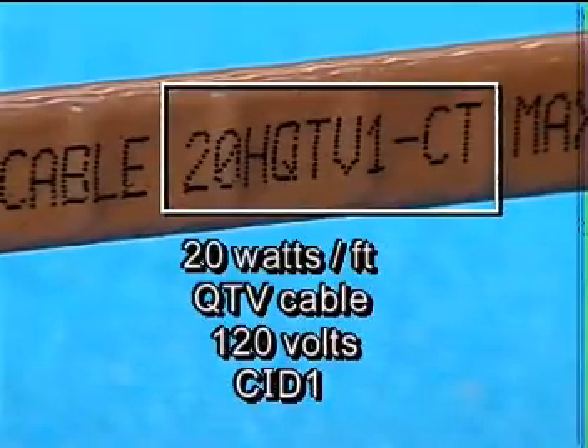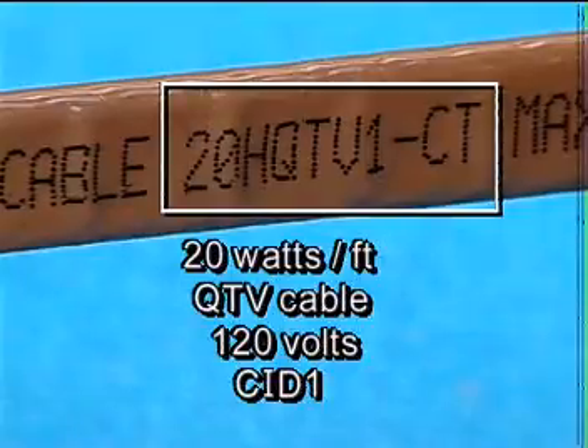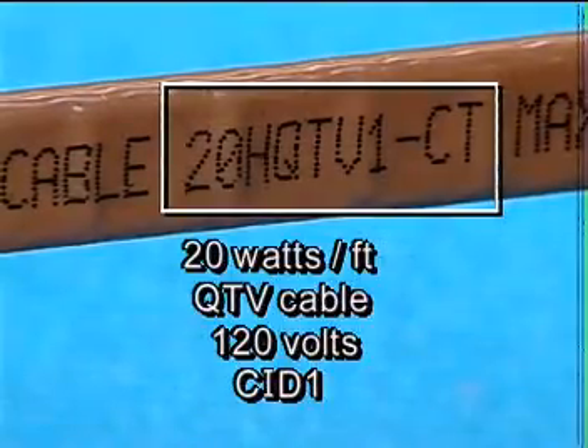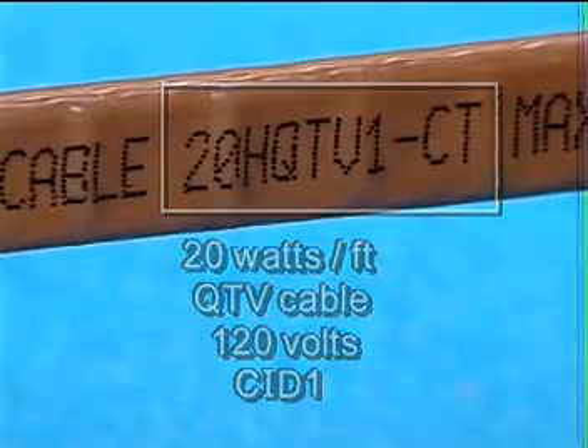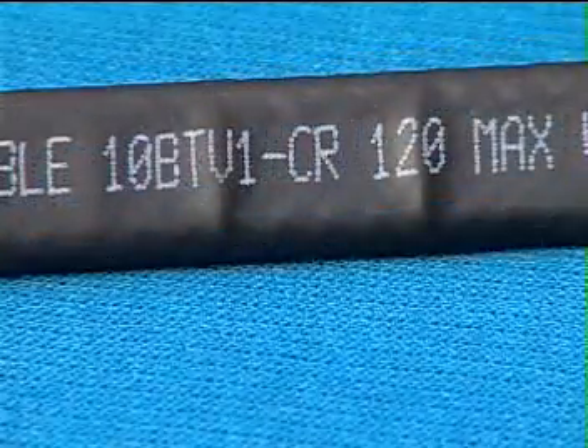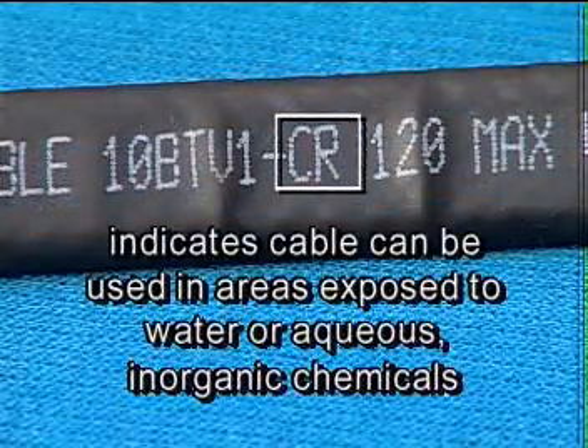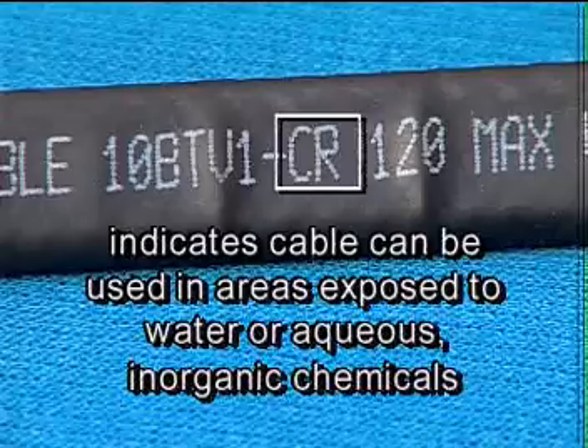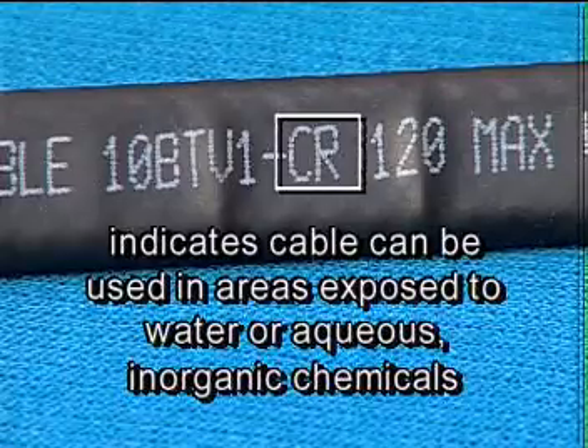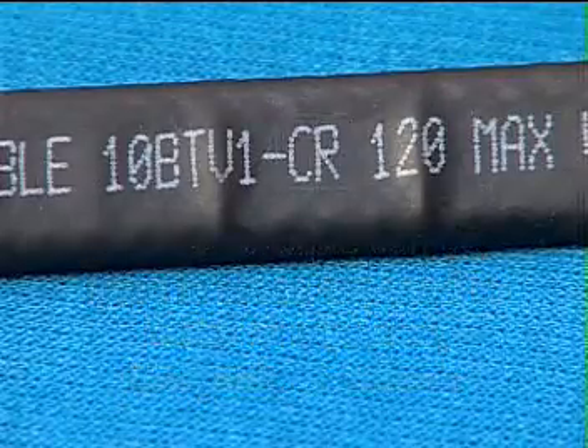20HQ-TV1-CT, for example, is a 20 watts per foot QTV heating cable for 120 volts and can be used in a Division 1 area. Some BTV cables may have CR printed on them. CR indicates that the cable can be used in areas exposed to water or aqueous inorganic chemicals.